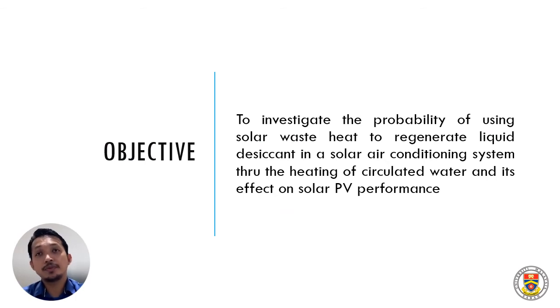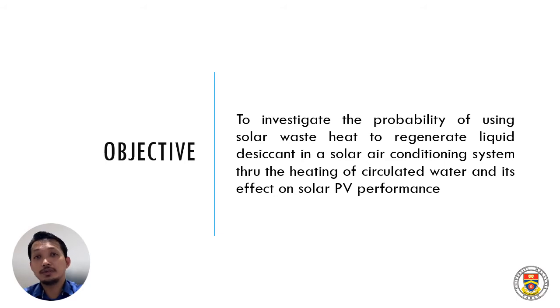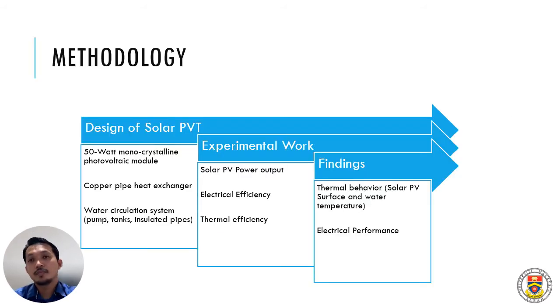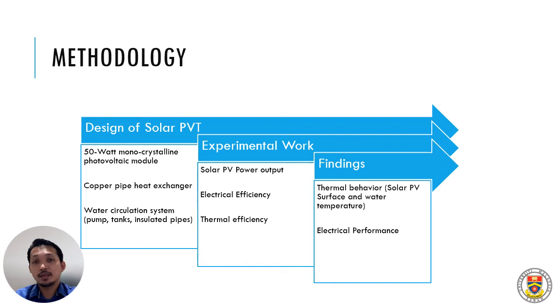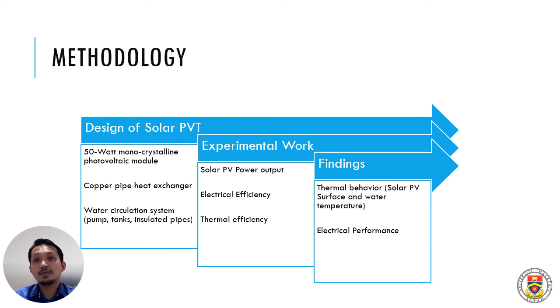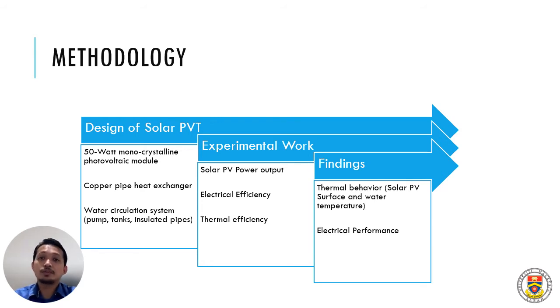The objective of this paper is to investigate the probability of using solar PV waste heat to regenerate liquid desiccant in a solar air conditioning system through the heating of circulated water and its effect on solar PV performance. There are three major steps to achieve this objective. The first is to design the solar PVT itself — we fabricate a copper tubing and attach it at the back of the solar PV. We use copper pipe as the heat exchanger, and then complete the experimental setup with a pump, tanks, and piping to circulate the water, then continue with the experimental work.